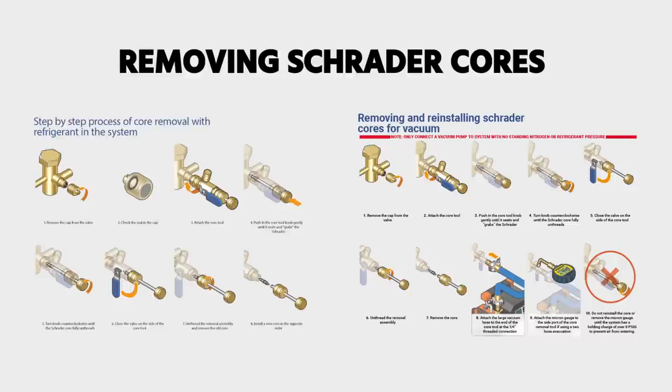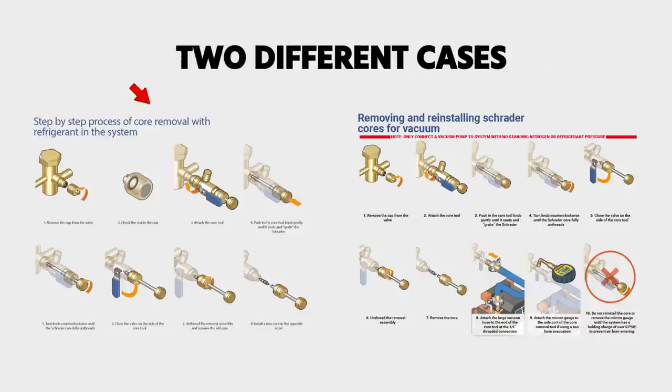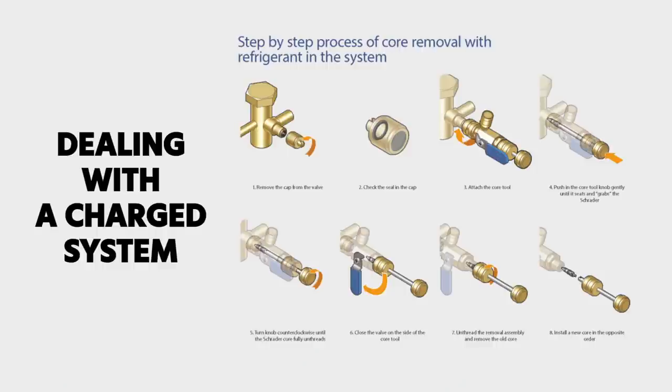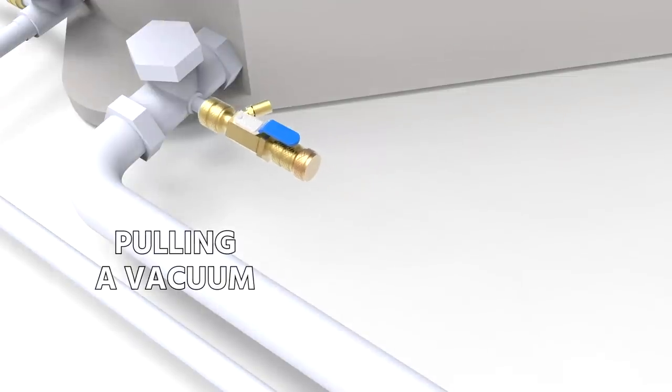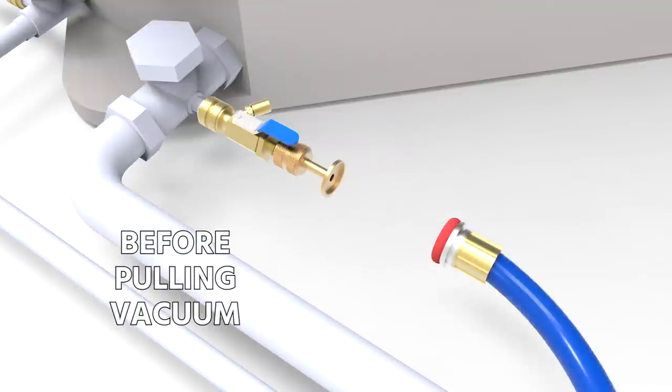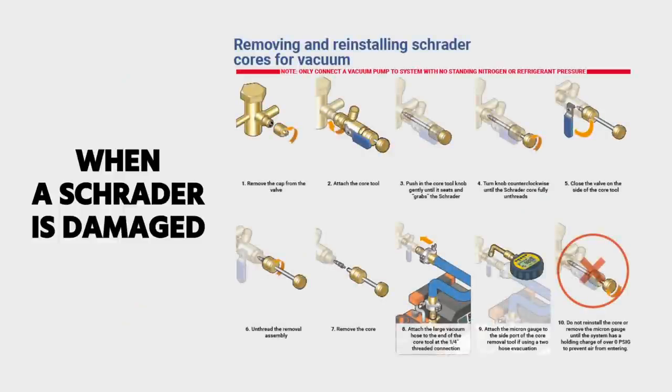In this video, I want to talk specifically about removing Schrader cores. There are two different cases when we want to do this. One is when we're dealing with a charged system and we want to pull the Schrader out under pressure. The other is when we want to do it when we're going to pull a vacuum. We always recommend removing all Schraders when you're going to pull a vacuum, when you're recovering, or when a Schrader is damaged.